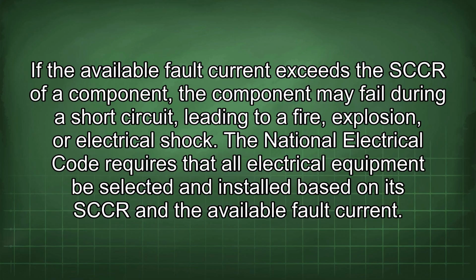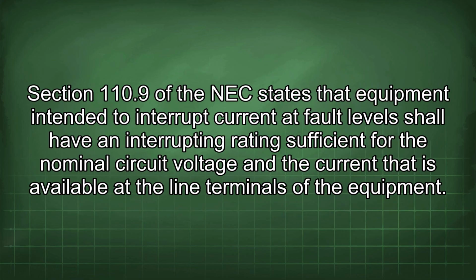The National Electrical Code requires that all electrical equipment be selected and installed based on its SCCR and the available fault current. Section 110.9 of the NEC states that equipment intended to interrupt current at fault levels shall have an interrupting rating sufficient for the nominal circuit voltage and the current that is available at the line terminals of the equipment.